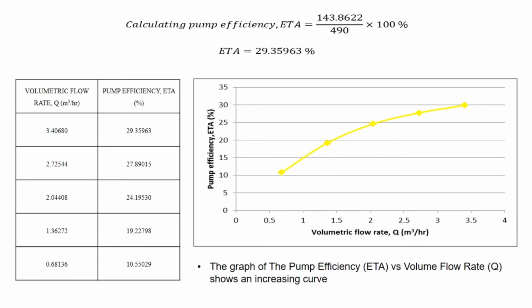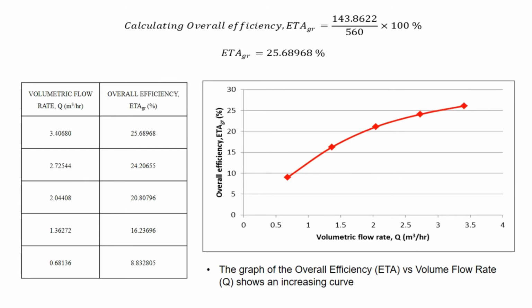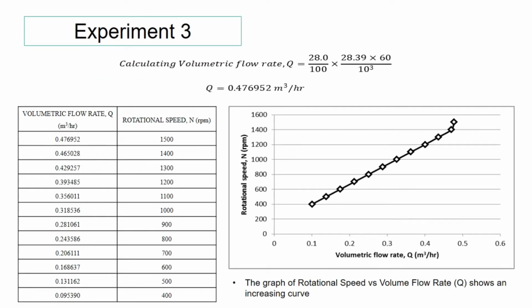To calculate the pump efficiency, the pump power output must be divided by the pump power input and times by 100 to get its percentage of pump efficiency. To calculate the overall efficiency, the pump power output is divided by 560, which is the total pump power input, and times by 100% to get the overall efficiency or percentage. For experiment 3, we have speed, flow rate, percentage of flow rate, and the differential pressure for pump 3.